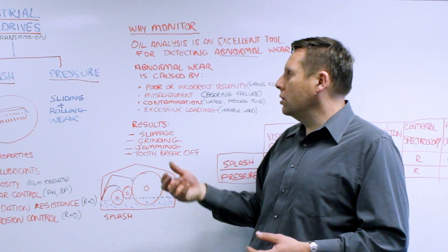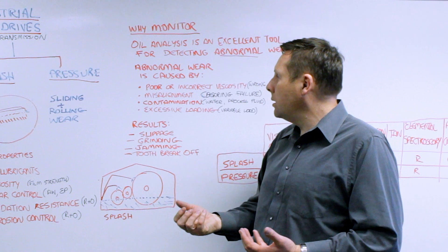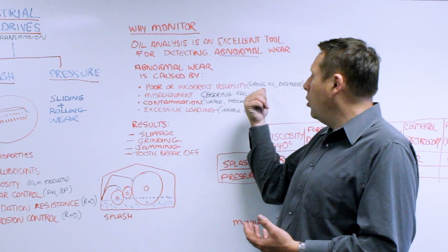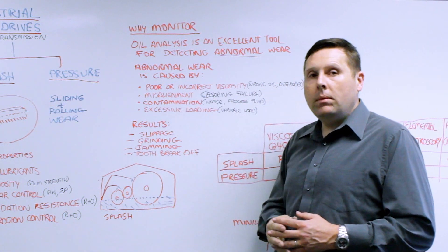Abnormal wear is caused when you have poor or incorrect lubricant. That could be because the viscosity is wrong, wrong oil, or it's degraded. You can have a misalignment issue.